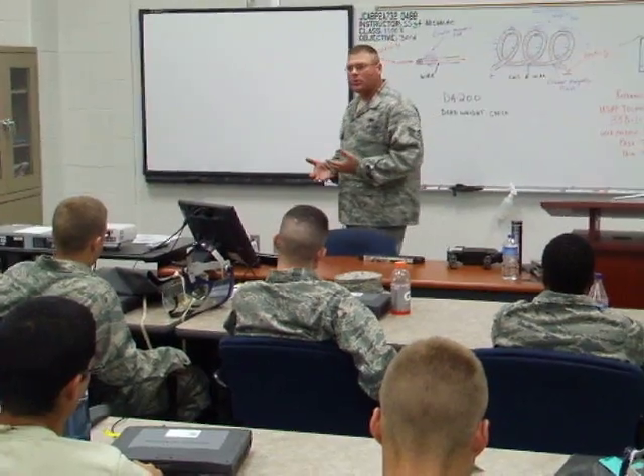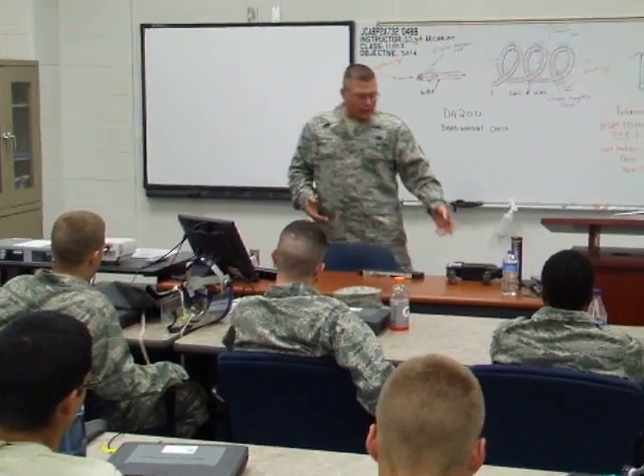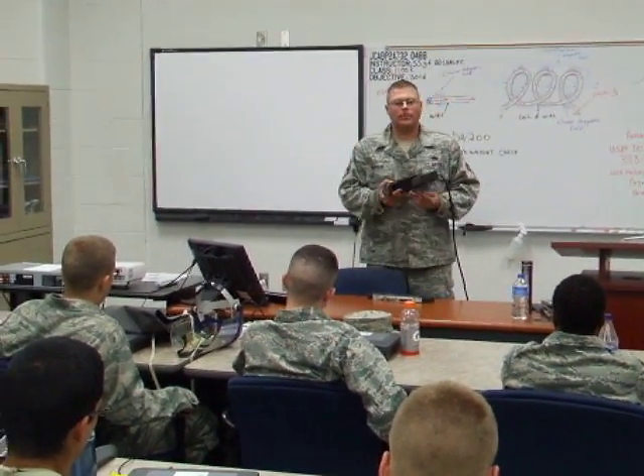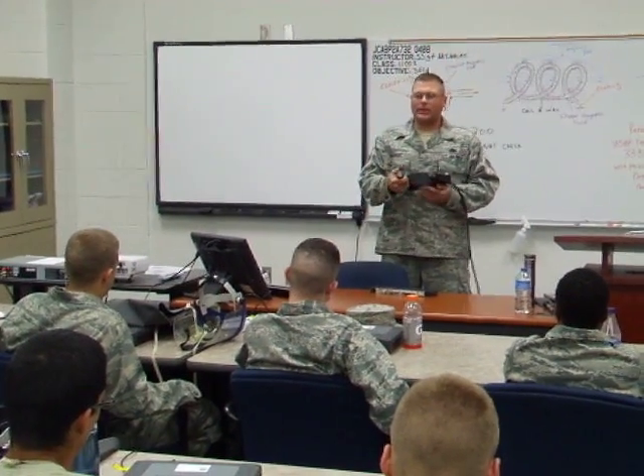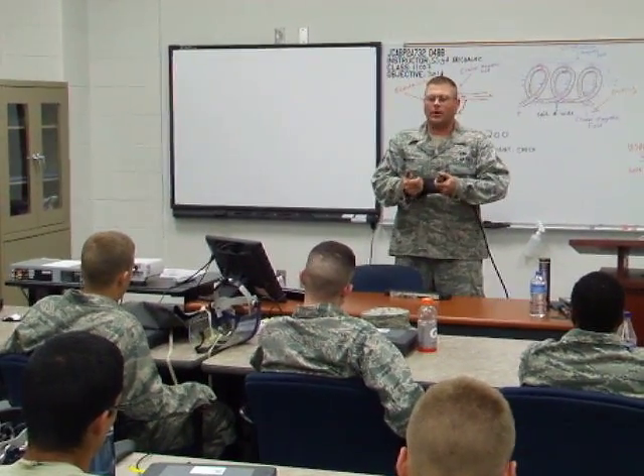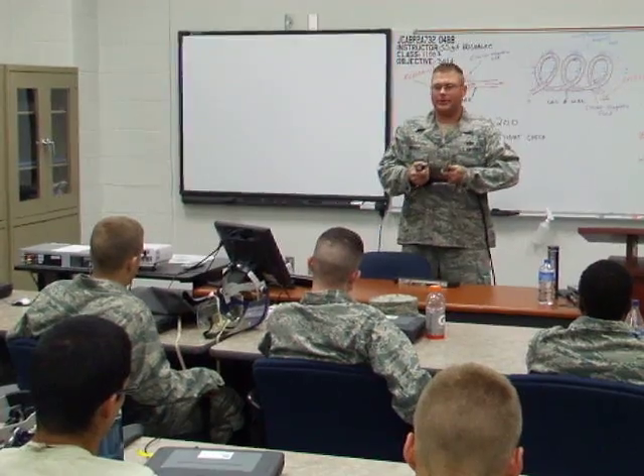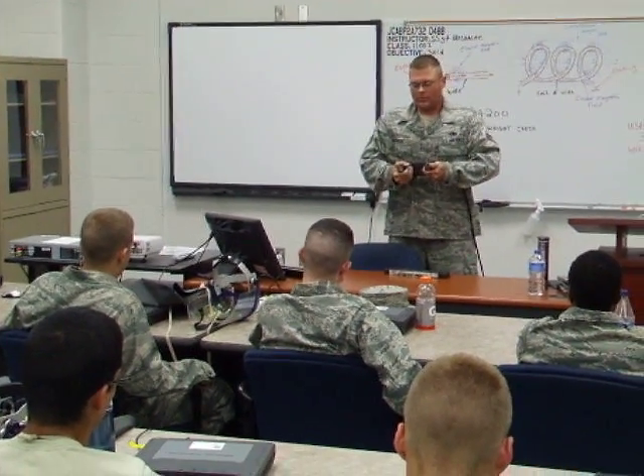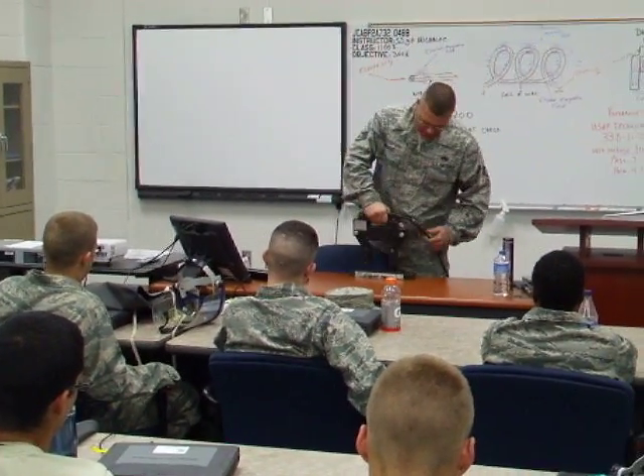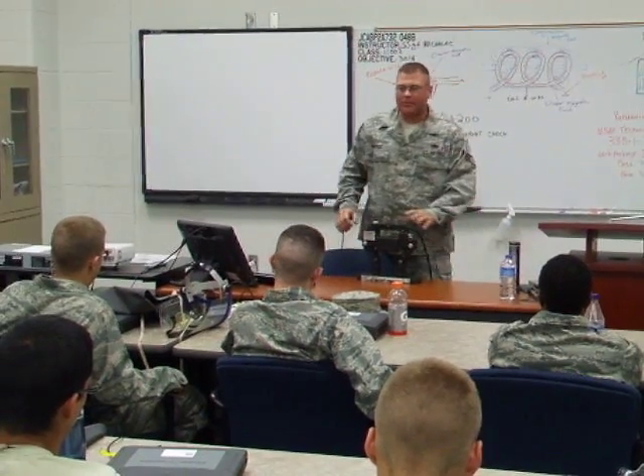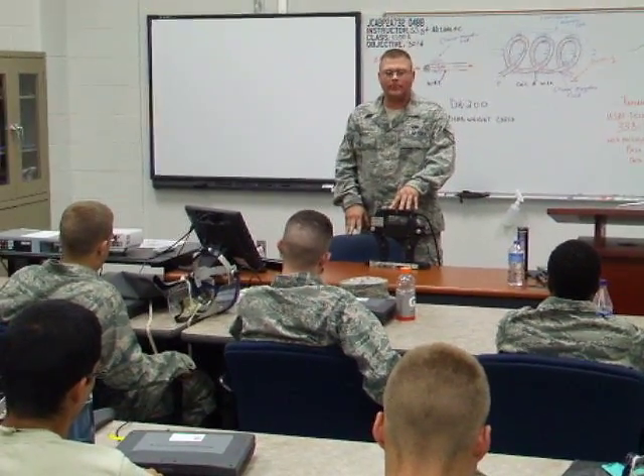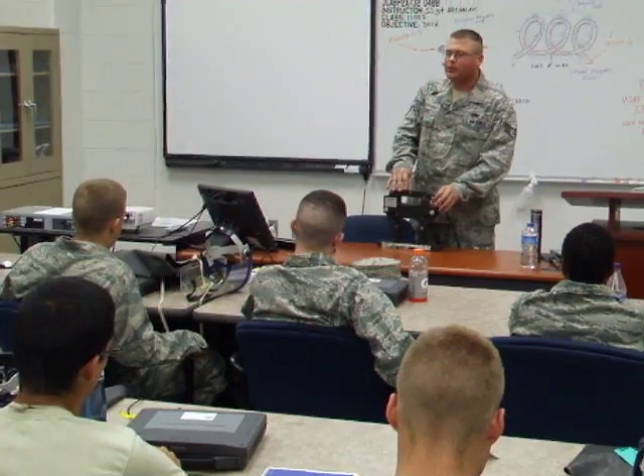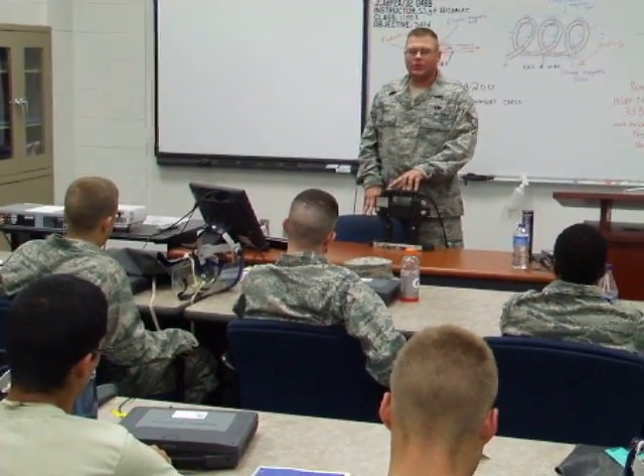The steps are simple. You're going to take your DA200 Parker probe, you're going to use these metal ceramic legs, and you're going to form them to where they are 2 to 4 inches apart from each other. Then you're going to place your DA200 Parker probe on top of your 10-pound weight. You're going to change your selector knob to alternating current. You're going to depress the trigger and hold it.